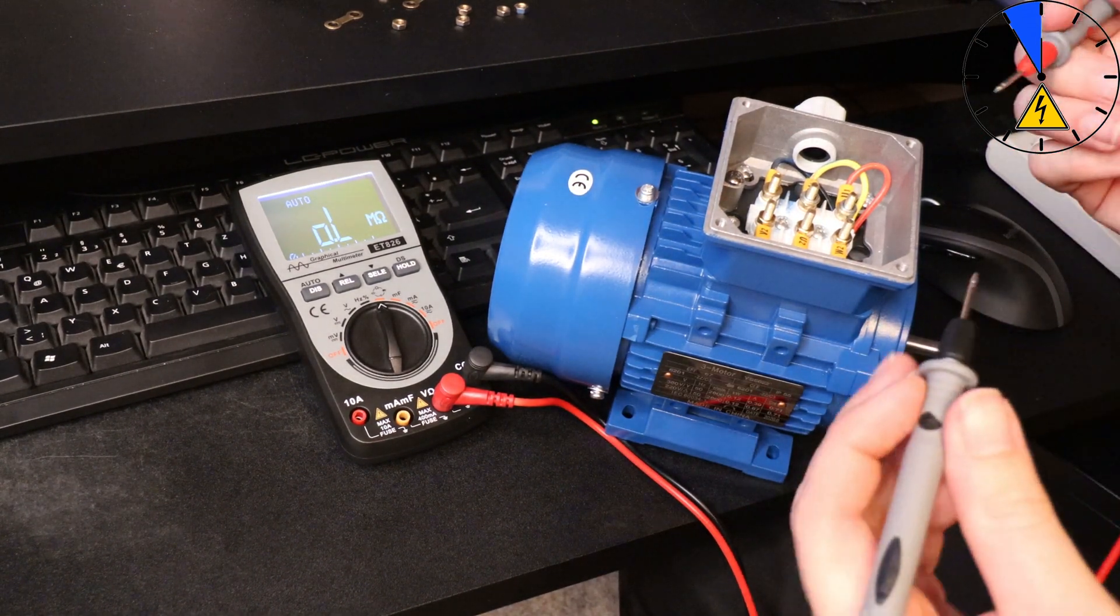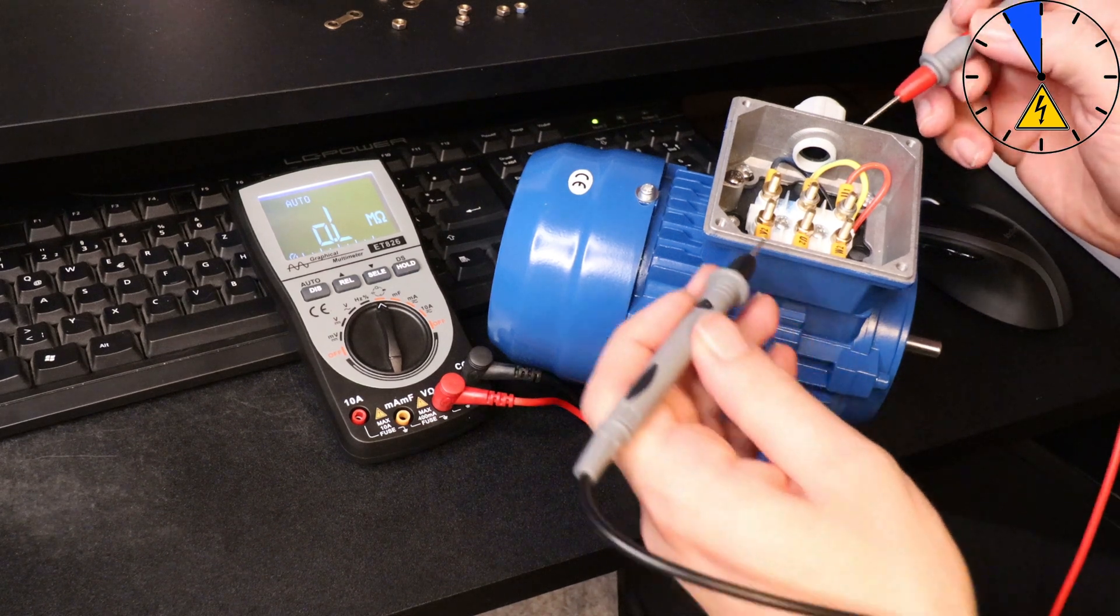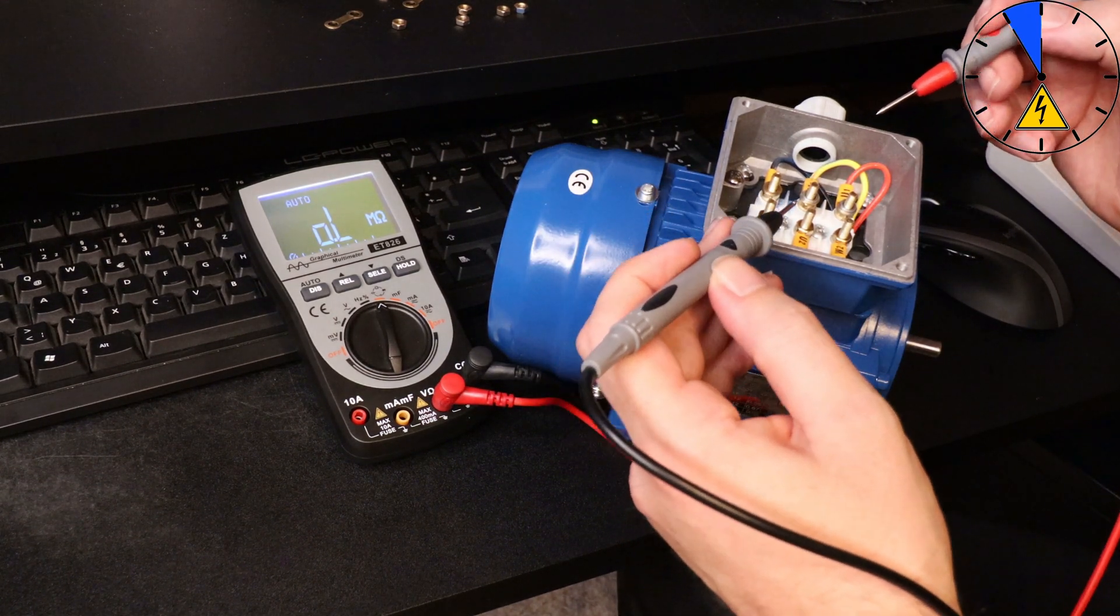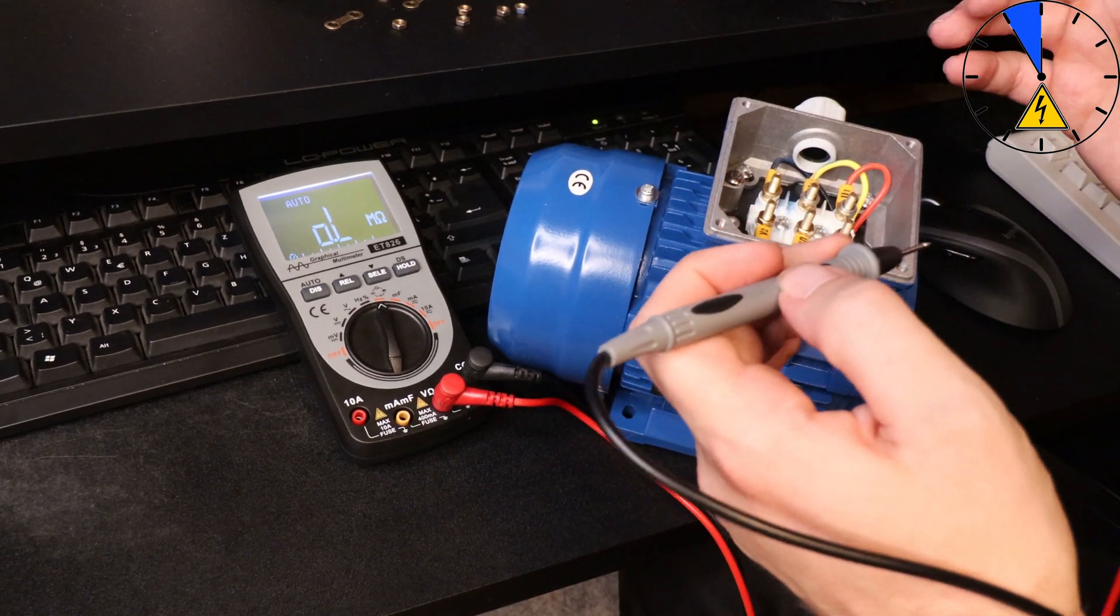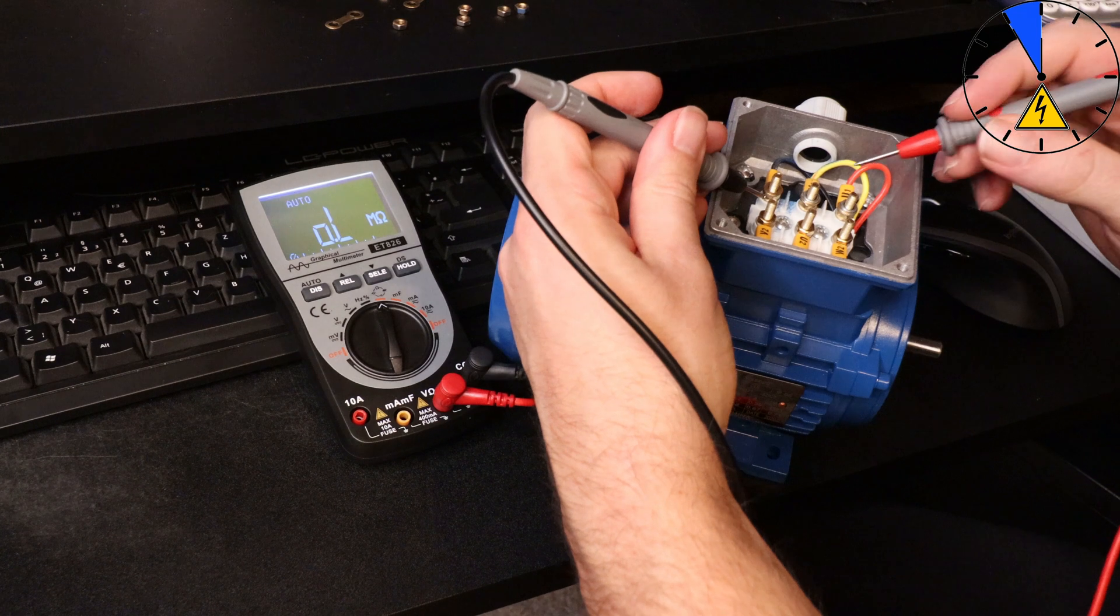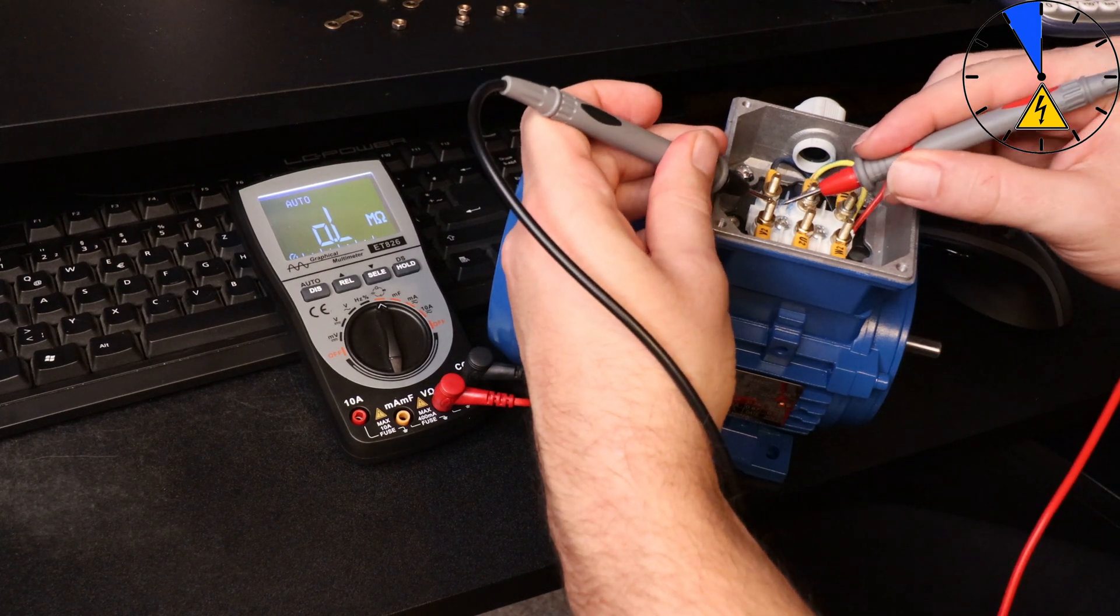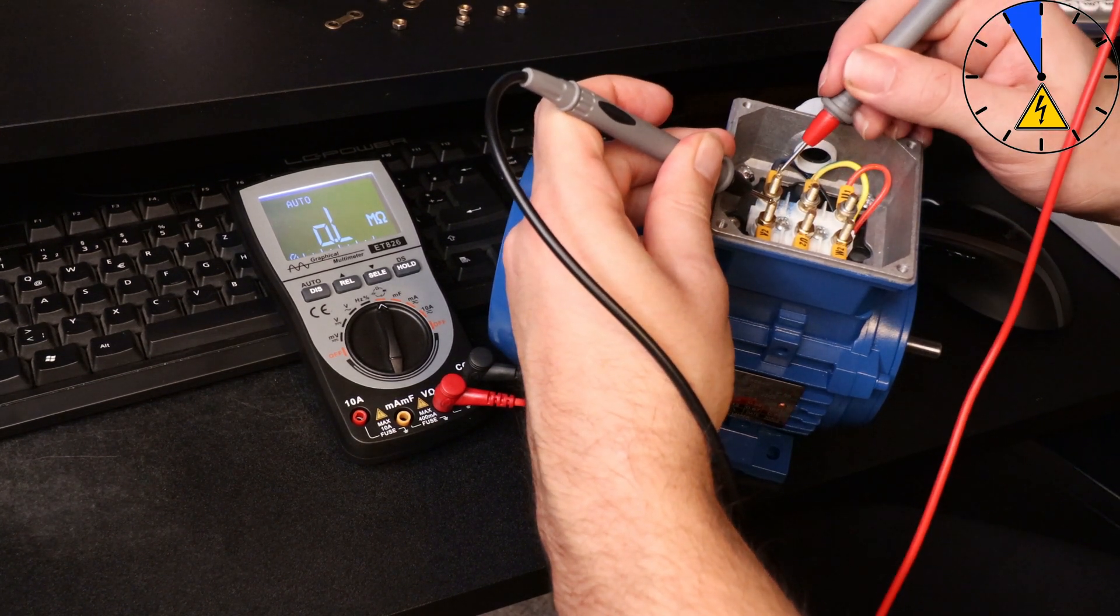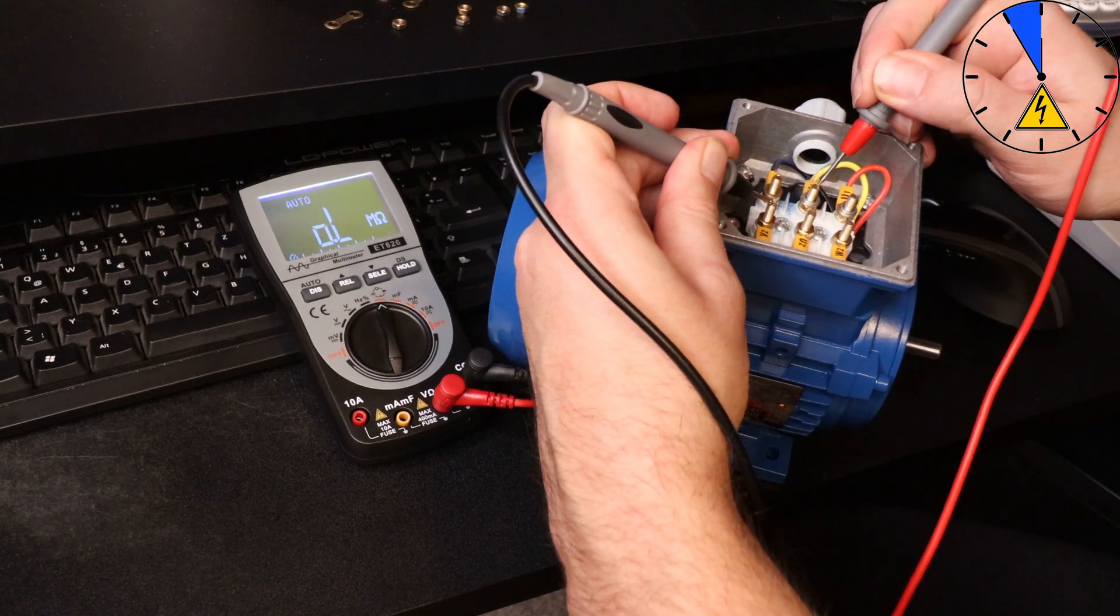This test passed. The next test, the last test is, is there a short circuit between one coil to another coil. So I go from here, from V2 to W1 to V1.